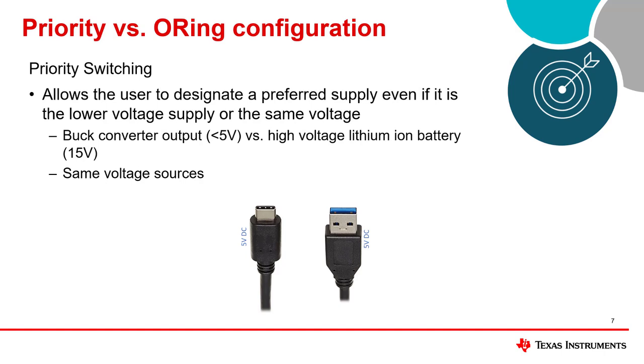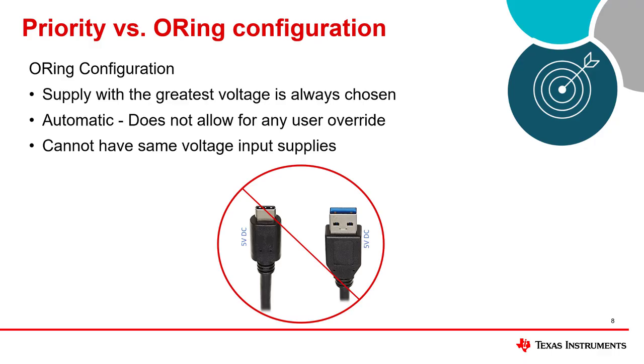A priority configuration allows the user to set a supply to be prioritized regardless of its voltage. For instance, if you have a battery at a higher voltage than your wired connection, you wouldn't want the battery to drain first. A priority configuration is also needed for systems which have the same input voltage supply, so that a constant evaluation of which supply is greater is not occurring. An ORing configuration instead always chooses the greater supply to deliver power to the load. This is a type of automatic switchover which does not allow for any user override, and should only be chosen when the two input supplies are not the same and the greater input power supply is always preferred.